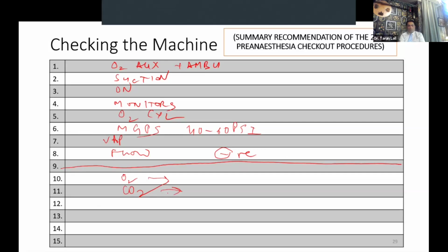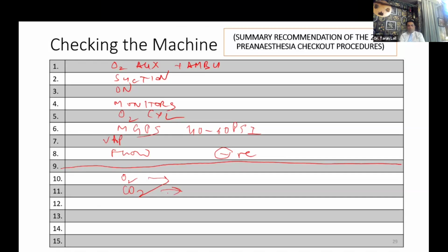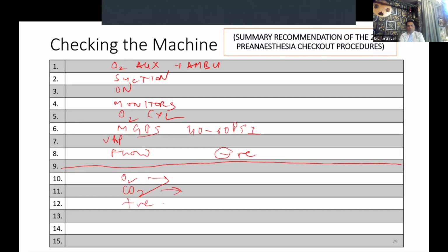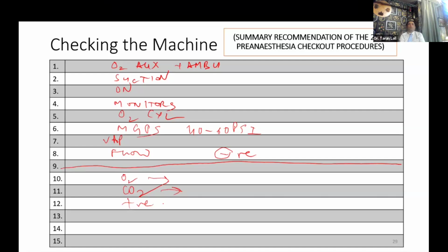The color, as I showed you, then there should be no channels, and it should not be dry. Then once we have done this, we come to step 12, which is your positive pressure leak test. Now you pressurize your system and see whether there is any leak, so you have to sustain a pressure of 30 centimeter water for 10 seconds. If you have done that, then you are sure that there is no leak.